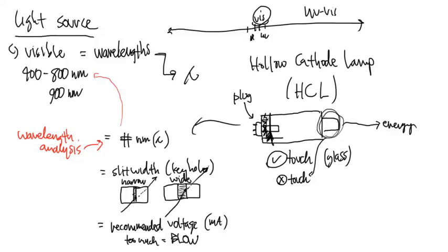So you have to make sure that you're at the recommended voltage of the lamp. And they're all different because they're all reading different metals which behave in a different way. So that voltage you have to dial in on. You have to make sure in the software that it perfectly matches before you use the bulb itself.